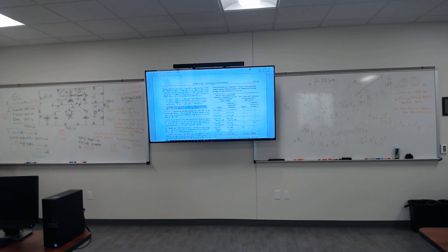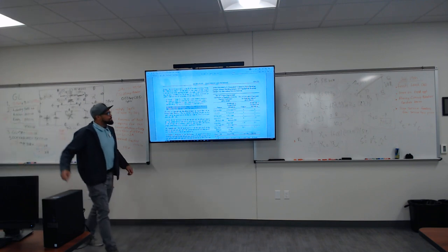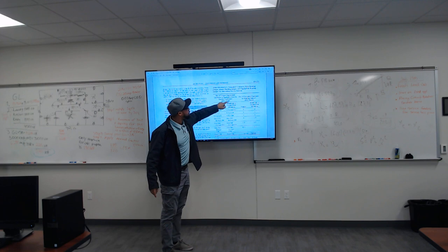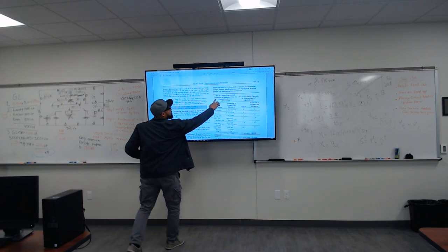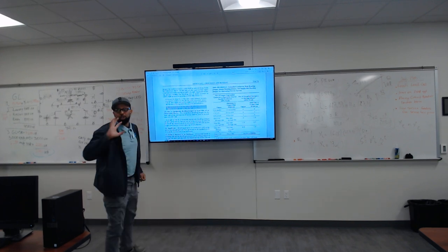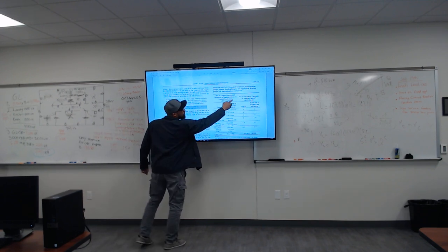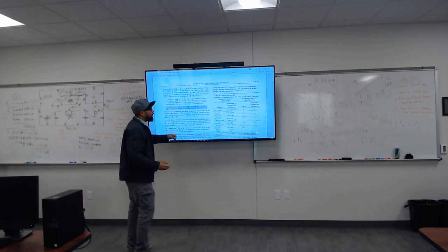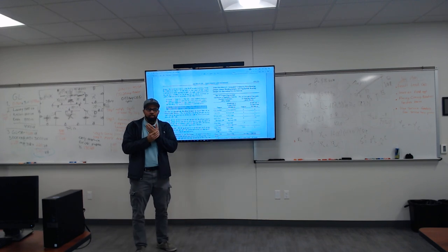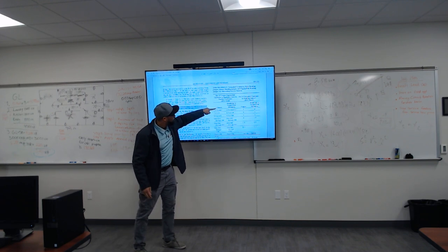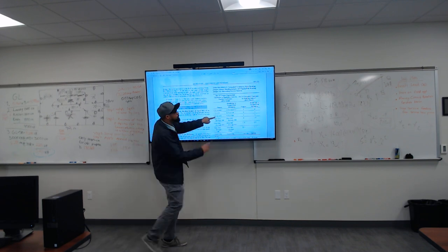All right, now, Mr. Panel, listen up. Anyone ask me what I got to do? Size of the largest ungrounded conductor or equivalent area for parallel conductors. The largest ungrounded, that's the service conductor we calculate, okay? So what size was our service conductor, fellas? 2 AWG. 2 AWG, so let's find copper. Of course, we're using copper. Copper, 2 AWG, all right?